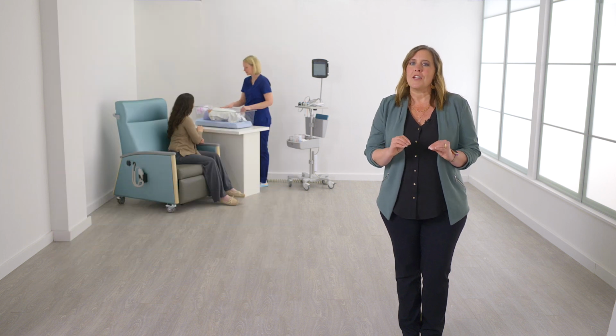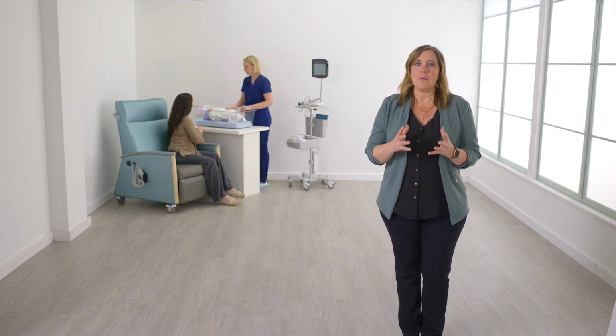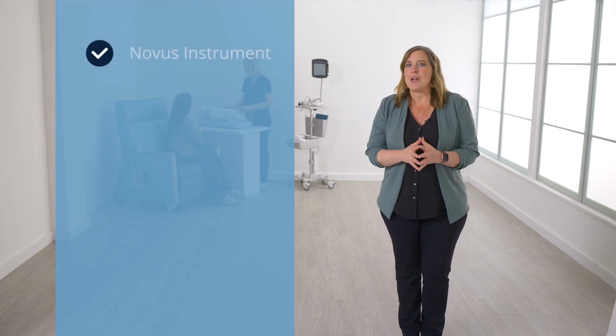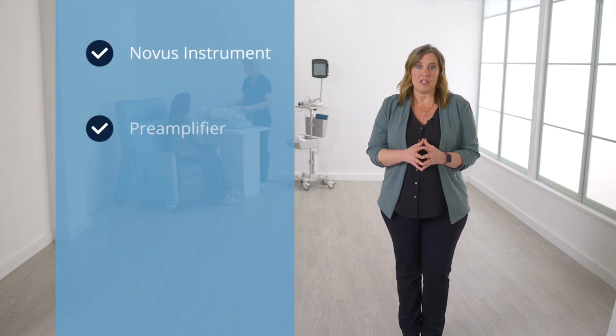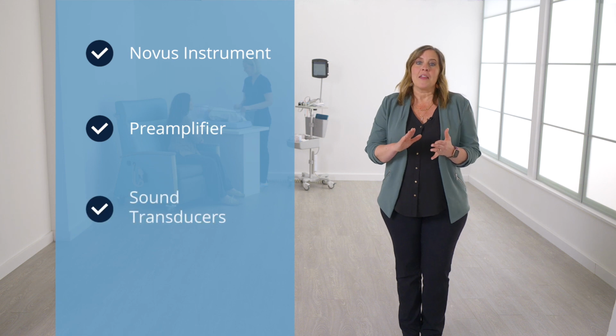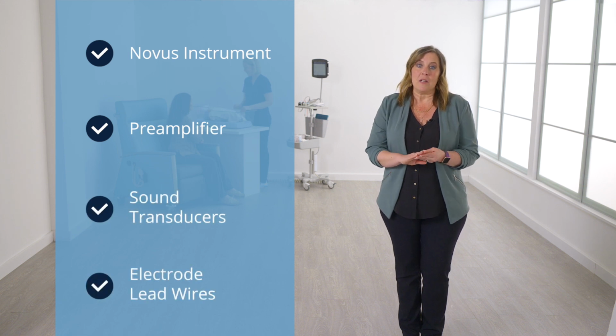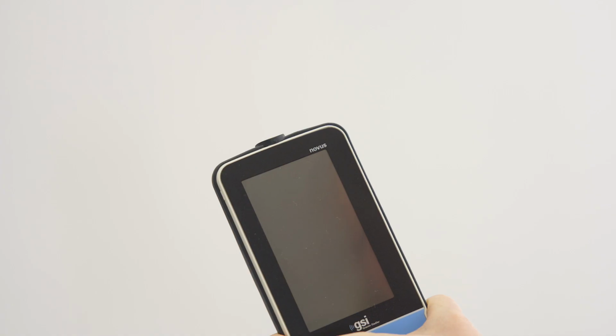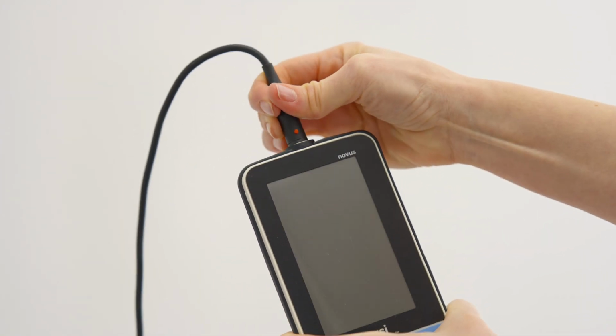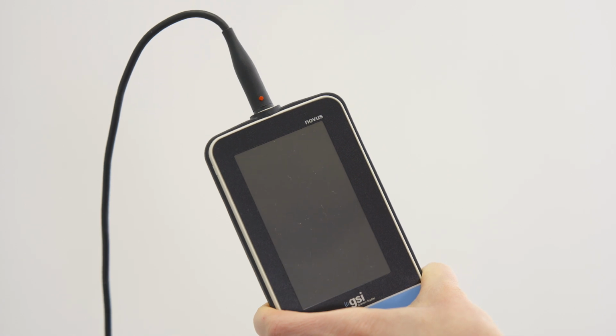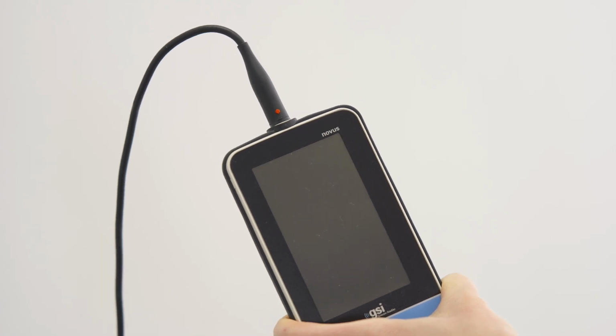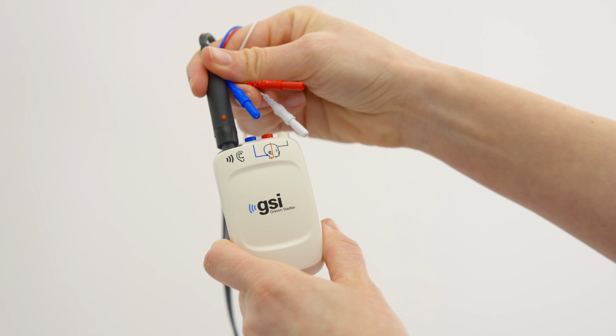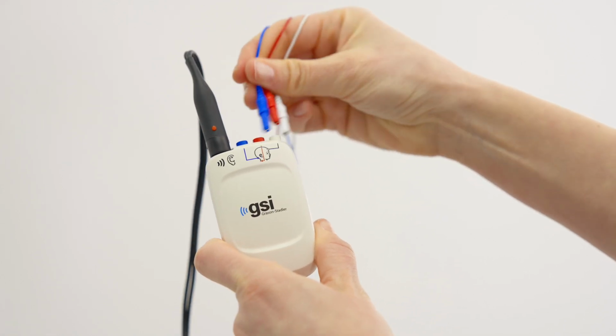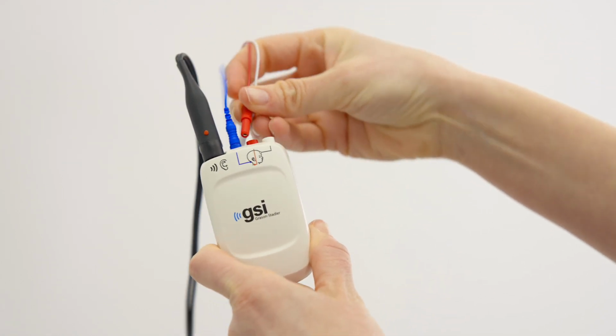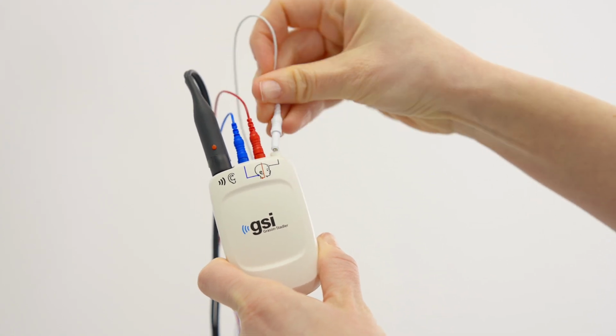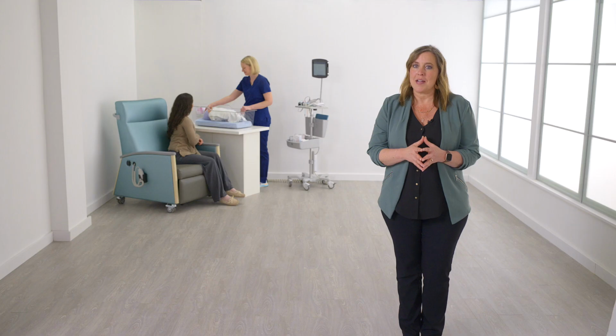To perform ABR testing with the Novus, gather the appropriate components and assemble. For ABR testing, you will need the Novus handheld instrument, the preamplifier, the sound transducers, and the electrode lead wires. Connect the preamplifier to the Novus by aligning the red dot on the cable to the red dot on the connector socket at the top of the Novus. Then plug the transducer, probe or insert earphones, to the preamplifier with the red dot facing up. Finally, connect the red, white, and blue electrode lead wires to the same color sockets on the preamplifier.